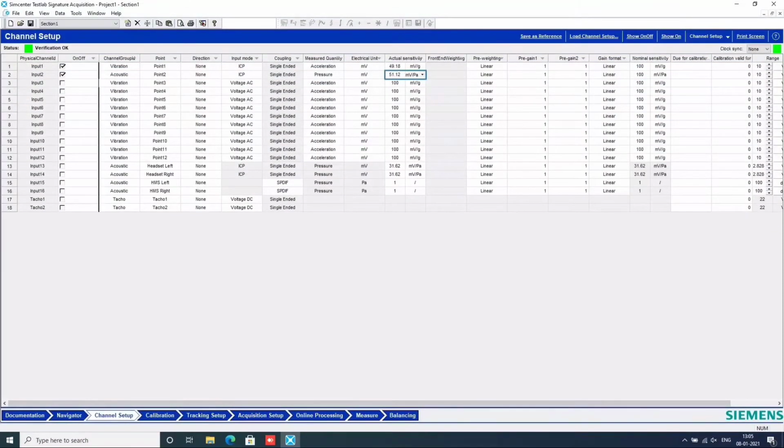There are also some of these setups that allow the transducer electronic data sheet, typically called the TEDS, wherein the calibration or the sensitivity values are saved into a data sheet inside the transducer, which can be read from the software directly. It will be very useful when you have large counts of measurement, like hundreds of measurements simultaneously. Having this electronic data sheet built into the transducer will be a very useful tool.